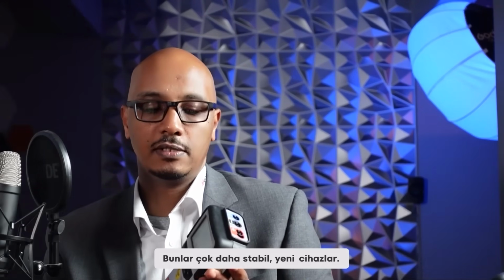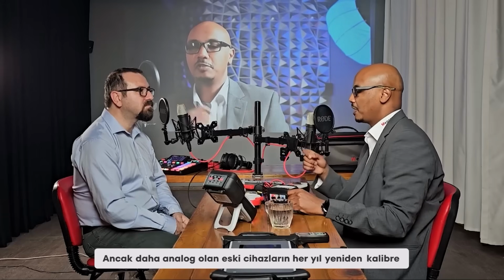The devices, the old Megger devices before the digital technology, you have to calibrate every year. Every year? Have to, yes. These ones are a lot more stable, the new devices. So what we say is you still want to check the calibration, maybe check it like once a year. So you need like a reference resistance, and you just do the test, and there's a procedure of just checking at different voltages. You're seeing that the value is still within the tolerance that we give you, and it's fine. As soon as it goes outside of that, then you need to recalibrate. But it's very common that these devices, 3 years, 4 years, they still don't need to be calibrated because you just do the check. It's still within the spec, you're fine. But the older devices that were more analog, they needed to be recalibrated every year.